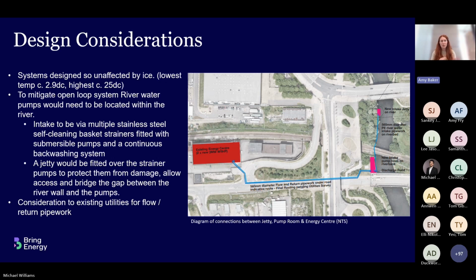We also decided to go for an open loop system in this case. The area is quite specific, the river wall is a lot higher up compared to the actual water flow, so there's a big drop between the edge of the river and where the water actually is. We needed to make sure the pumps were located within the river itself to mitigate this, meaning we'd have a permanently flooded suction rather than relying on priming systems. This results in positive pressures throughout the pipe network as it rises above the surface water level, and also aids air displacement. We decided that was the best route for that aspect.